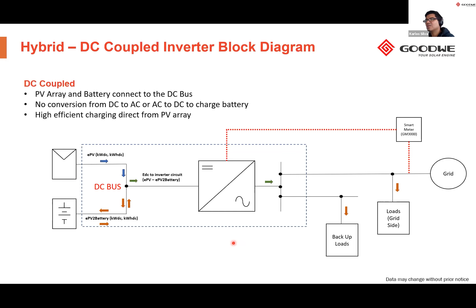Apart from a higher overall system efficiency, another advantage of a DC coupled system is that when there is a grid failure, in this scenario, if the grid went down during the day, the backup loads will continue to be powered from both the PV and the battery. And that will happen until the sun sets in the evening. So that's one major advantage of a DC coupled system in a backup mode scenario.